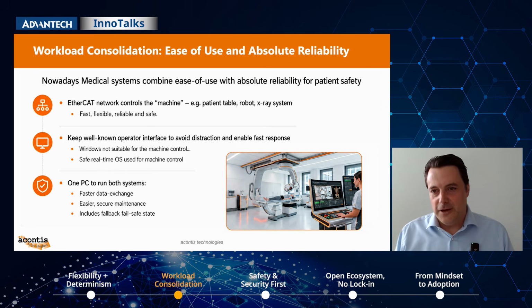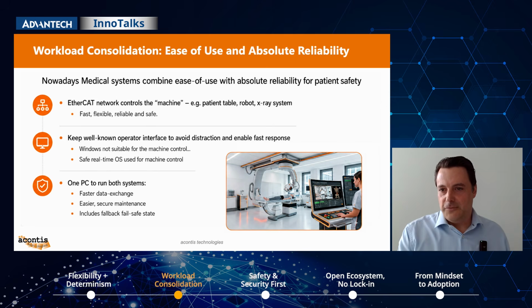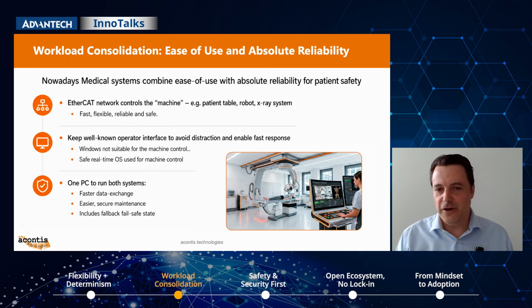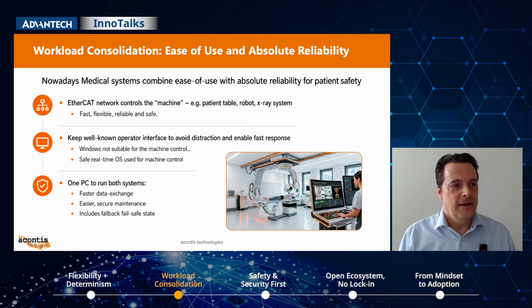It's the firewall built into the hypervisor, and another firewall built into the Windows, as well as separate firewalls, to really make sure that nobody can modify any of those safety-relevant data. And it also includes the fail-safe state in case of any errors. Again, the process data can be saved in non-volatile memory, while everything else can simply be rebooted. So the key is that the patient is always safe, but with maximum flexibility and user friendliness for the doctor.